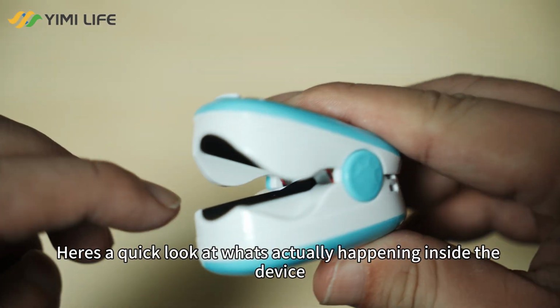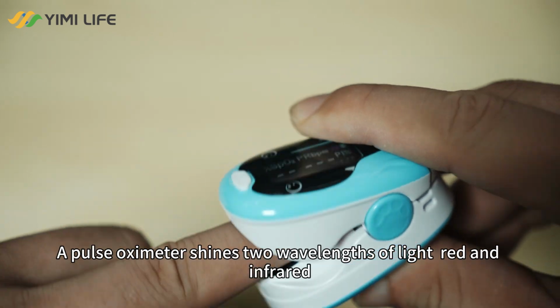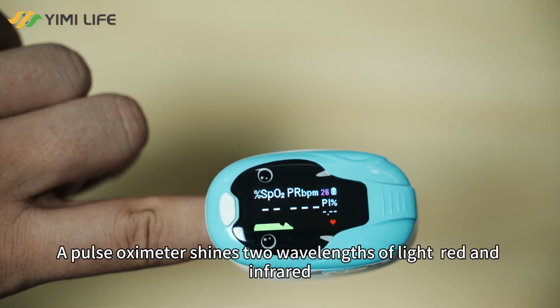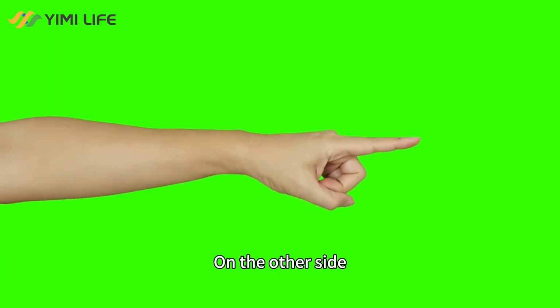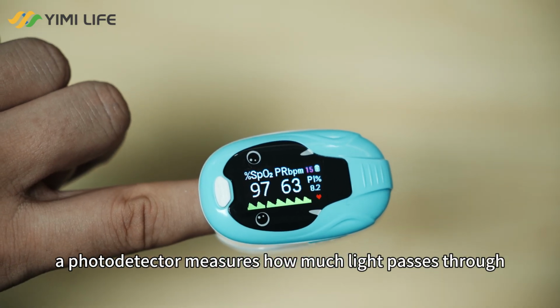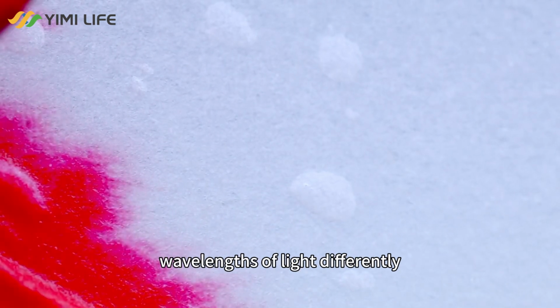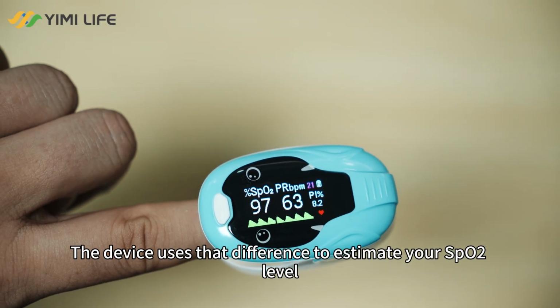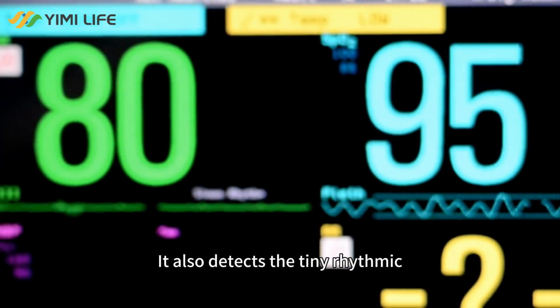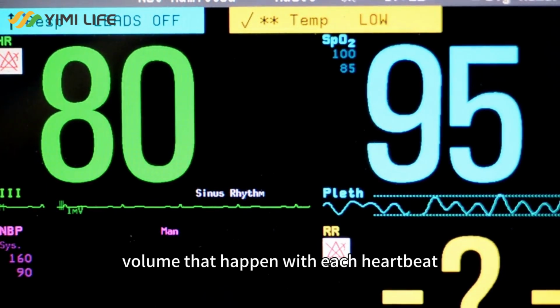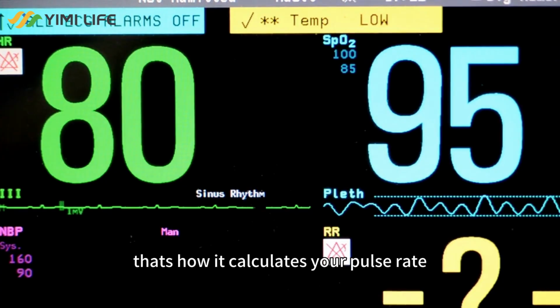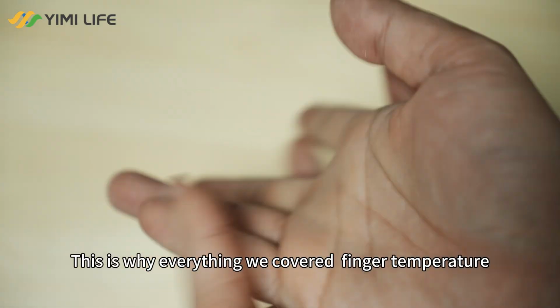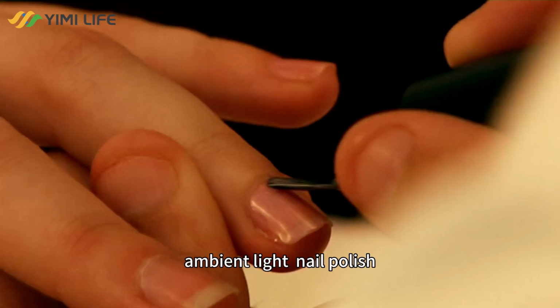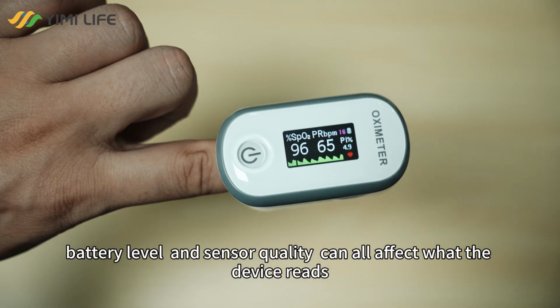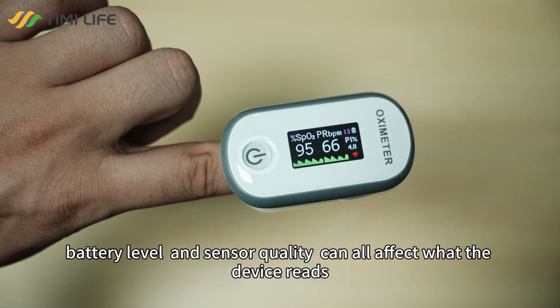Here's a quick look at what's actually happening inside the device. A pulse oximeter shines 2 wavelengths of light, red and infrared, through your fingertip. On the other side, a photodetector measures how much light passes through. Oxygenated and deoxygenated blood absorb these 2 wavelengths of light differently. The device uses that difference to estimate your SpO2 level. It also detects the tiny rhythmic changes in blood volume that happen with each heartbeat. That's how it calculates your pulse rate. This is why everything we covered, finger temperature, movement, position, ambient light, nail polish, battery level, and sensor quality can all affect what the device reads.